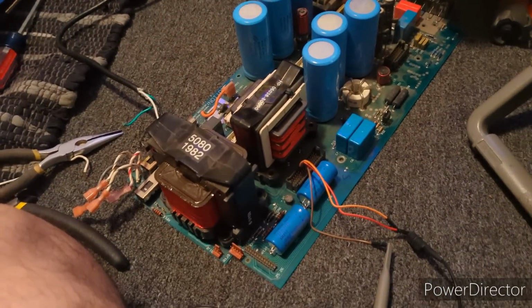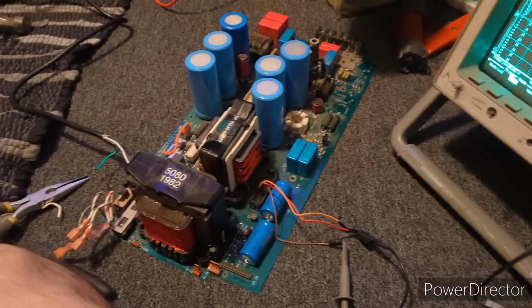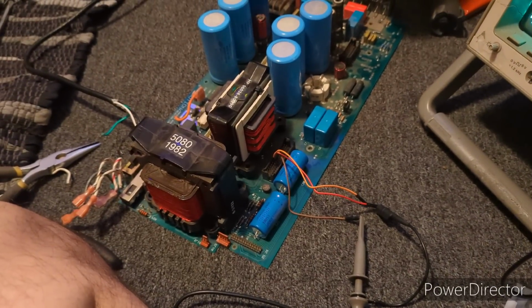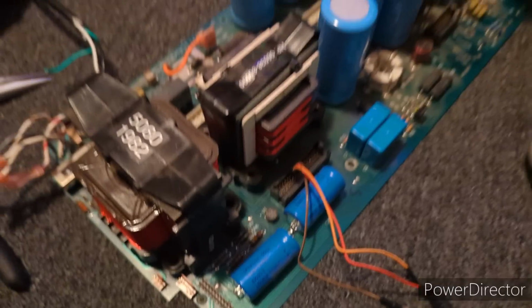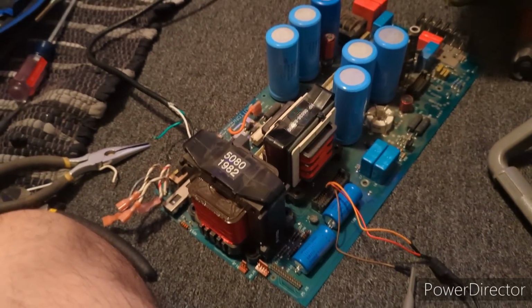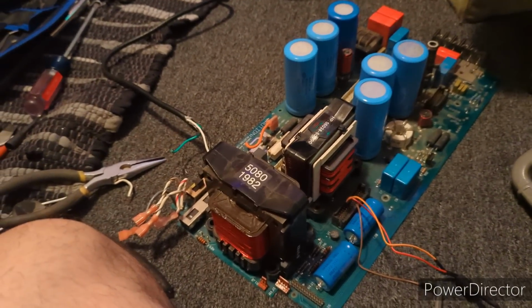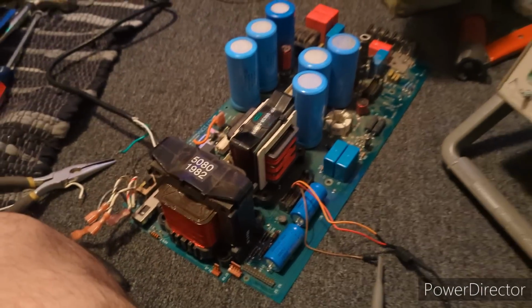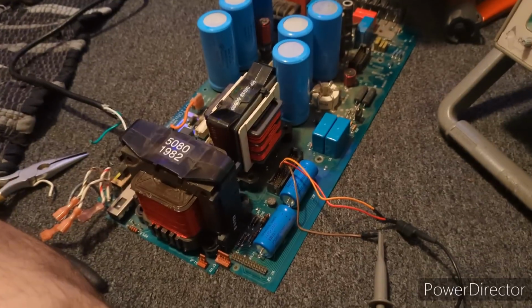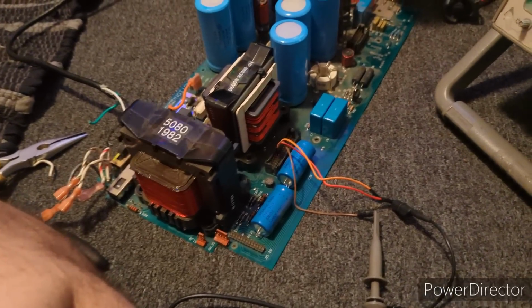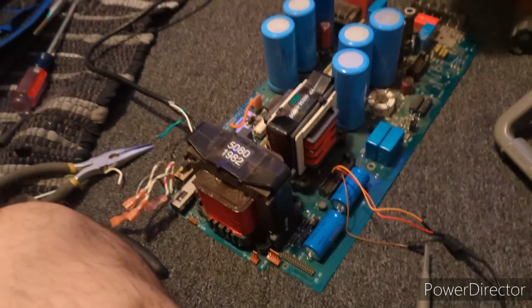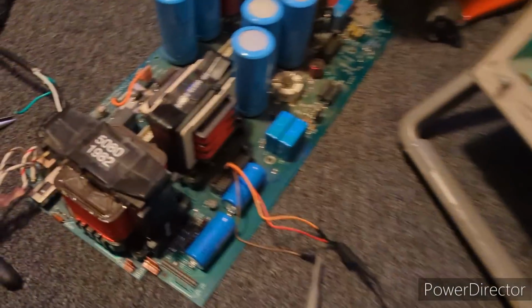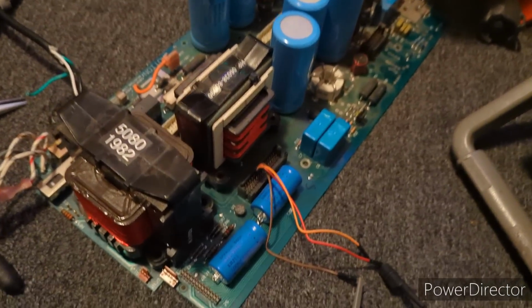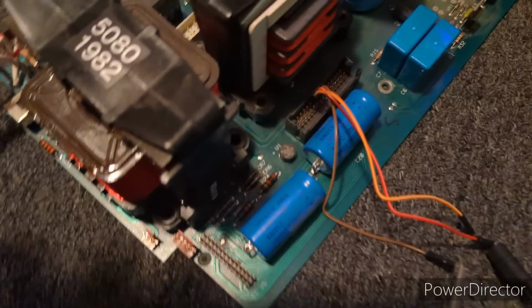Okay, so I wanted to see if I could narrow down where this fault was coming from. So, as we saw, clearly the board started releasing the magic smoke from those diodes, CR6 and CR7. And so I immediately turned it off. And then I wanted to start removing some of the boards to see if it would stop if I removed one. And so I removed the control board, and it stopped smoking. So it seems to be that there's an issue with that board, but I just wanted to take it a step further to see if the main board is providing that unregulated 20 volts. So right now I've got some jumper wires connected to pins 15, 17, and 19 on that connector right there.